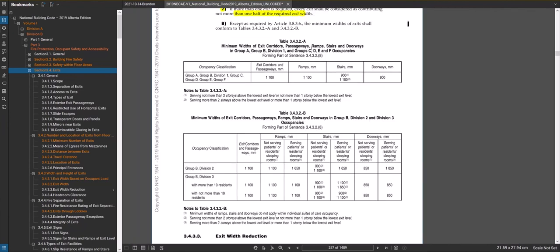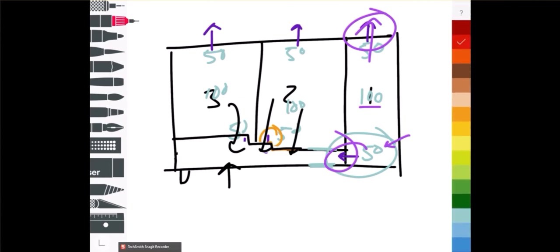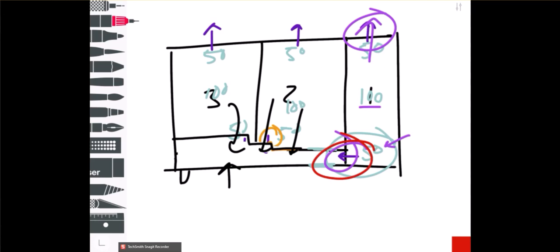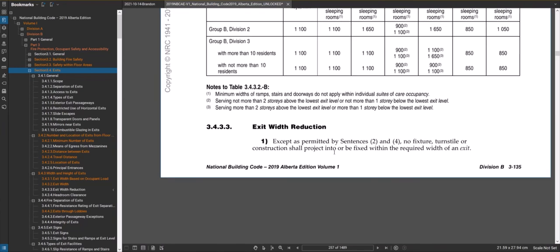Sometimes occupant loads are really quite low, so there are always going to be minimums. For example, if you have 50 people heading out a door, 50 times 6.1 only gives you a 305 millimeter wide door requirement — obviously you wouldn't do that. So there are minimums to find based on your group classification. For a doorway the minimum would be 800 millimeters for group E or group F, but normally you'd have a 900 millimeter door, and a single door leaf would satisfy the requirement.